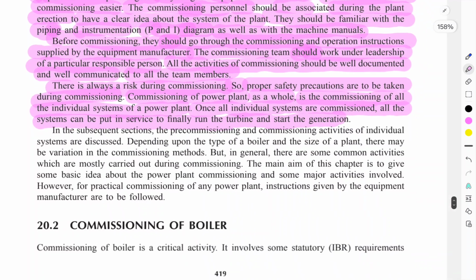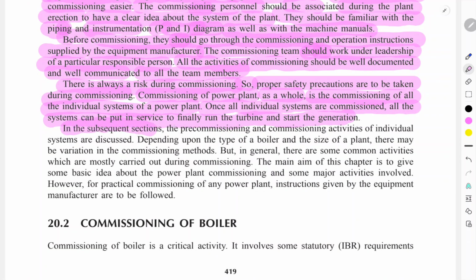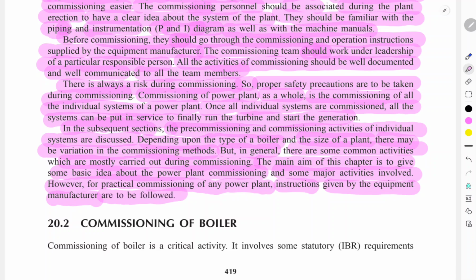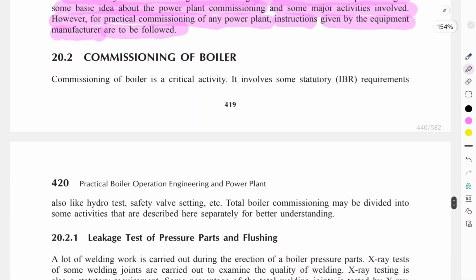Okay. Furthermore, in the subsequent sections, the pre-commissioning and commissioning activities of the individual systems are discussed. Depending upon the type of boiler and the size of the plant, there may be variation in the commissioning method, but in general there are some common activities which are mostly carried out during commissioning. The main aim of this chapter is to give some basic idea about power plant commissioning and the major activities involved. However, for the practical commissioning of any power plant, the instructions given by the equipment manufacturer are to be followed. So this is what we read about the commissioning.